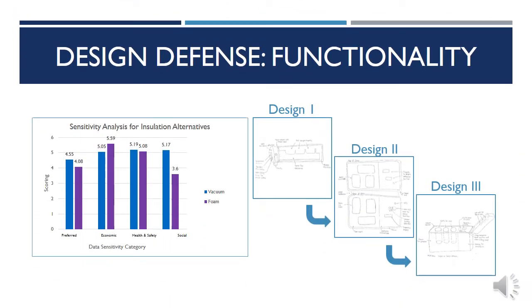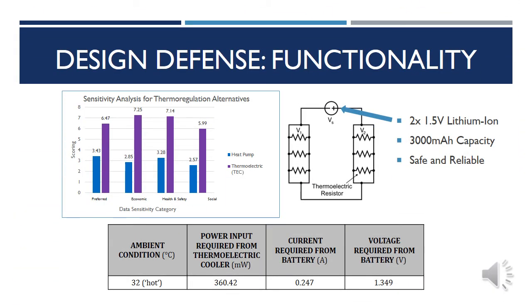The use of vacuum insulation was chosen as the primary method of insulation because it allows for the least amount of heat transfer. Stainless steel was used as our base material due to its properties of being strong as well as ductile. A rectangular prism shape was chosen over a cylindrical one because it allows for easier access of the vials and is more likely to be seen as a medical device as opposed to being mistaken for a water bottle. The lid was designed as a hinged top located on the second smallest side of the device, limiting the surface area exposed to the environment when opened while still allowing easy access to all three vials and the power supply.